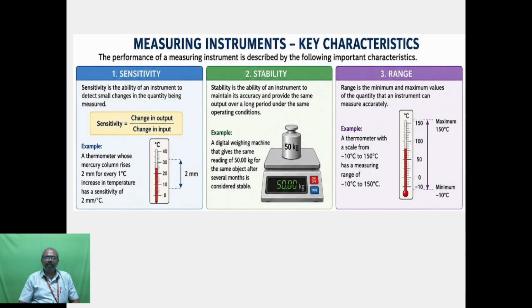For example, a digital weighing machine that gives the same reading of 50 kg for the same object being measured after several months is considered stable. Then range. Range is the minimum and maximum values of the quantity that an instrument can measure accurately. Example, a thermometer with a scale from minus 10 degree centigrade to 150 degree centigrade has a measuring range of minus 10 degree centigrade to 150 degree centigrade.